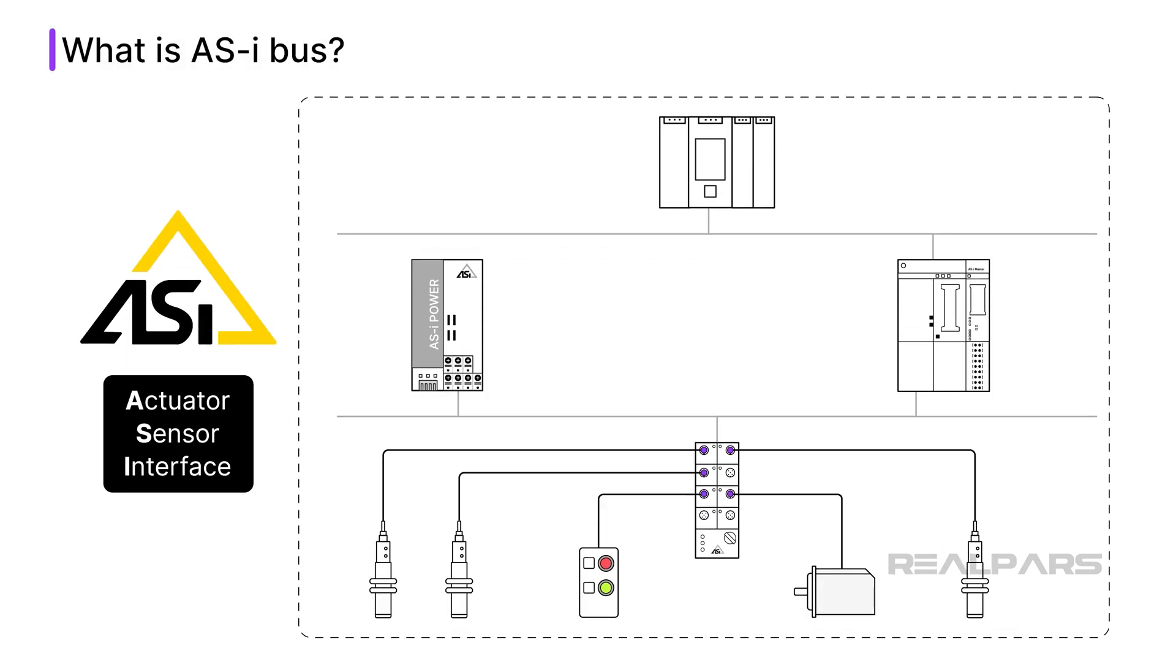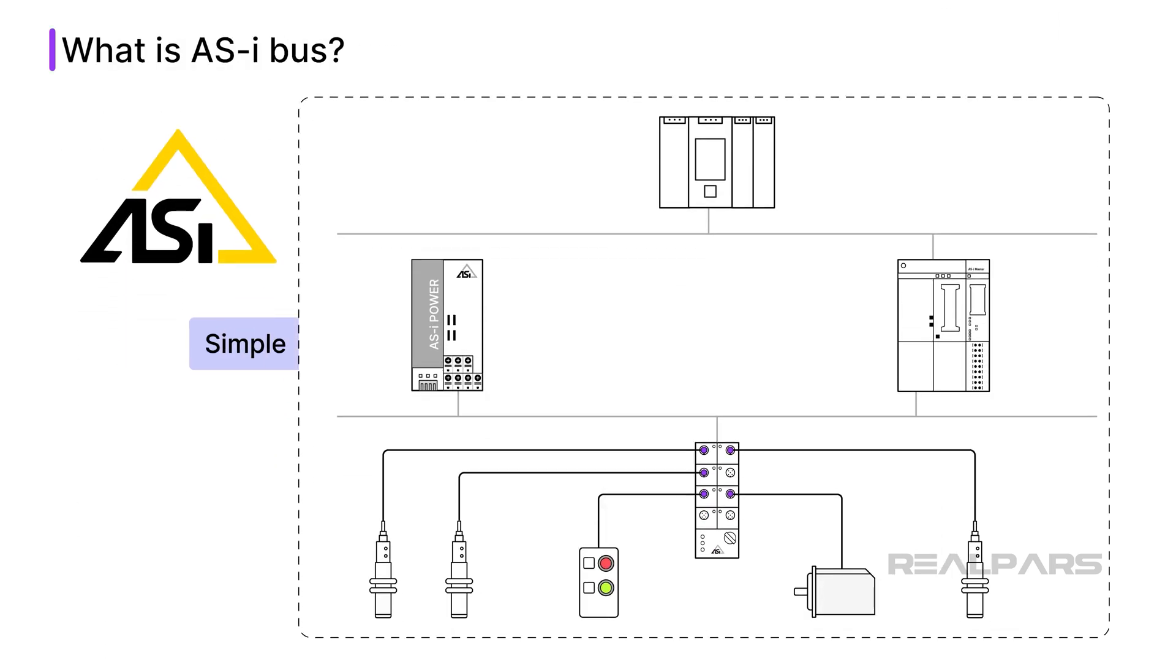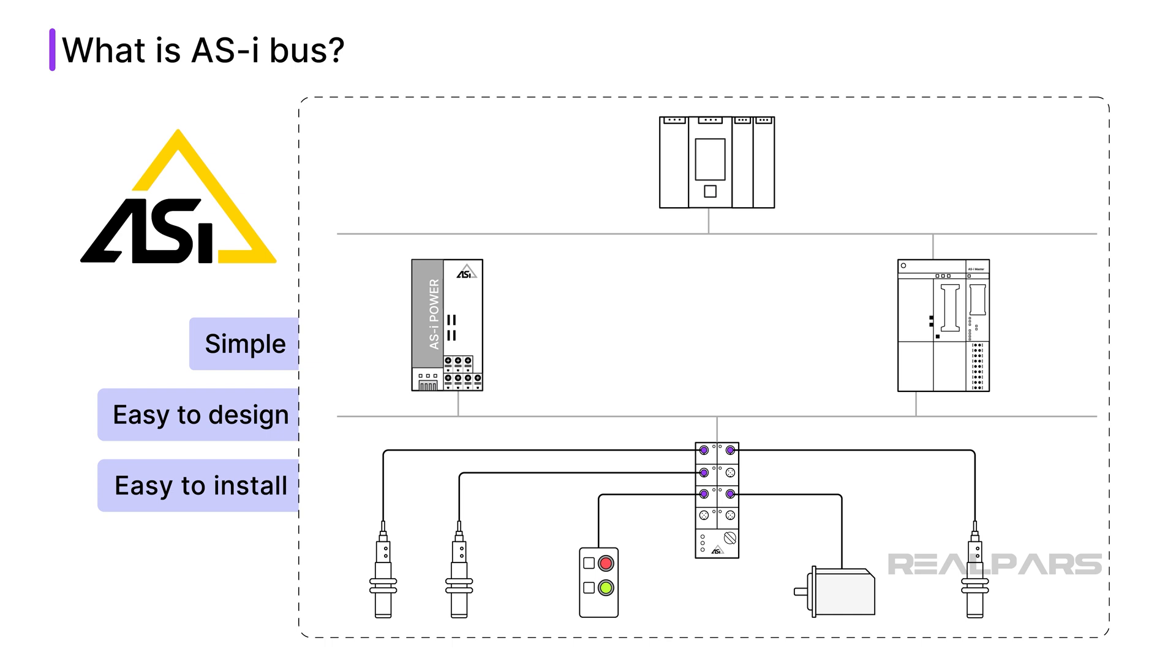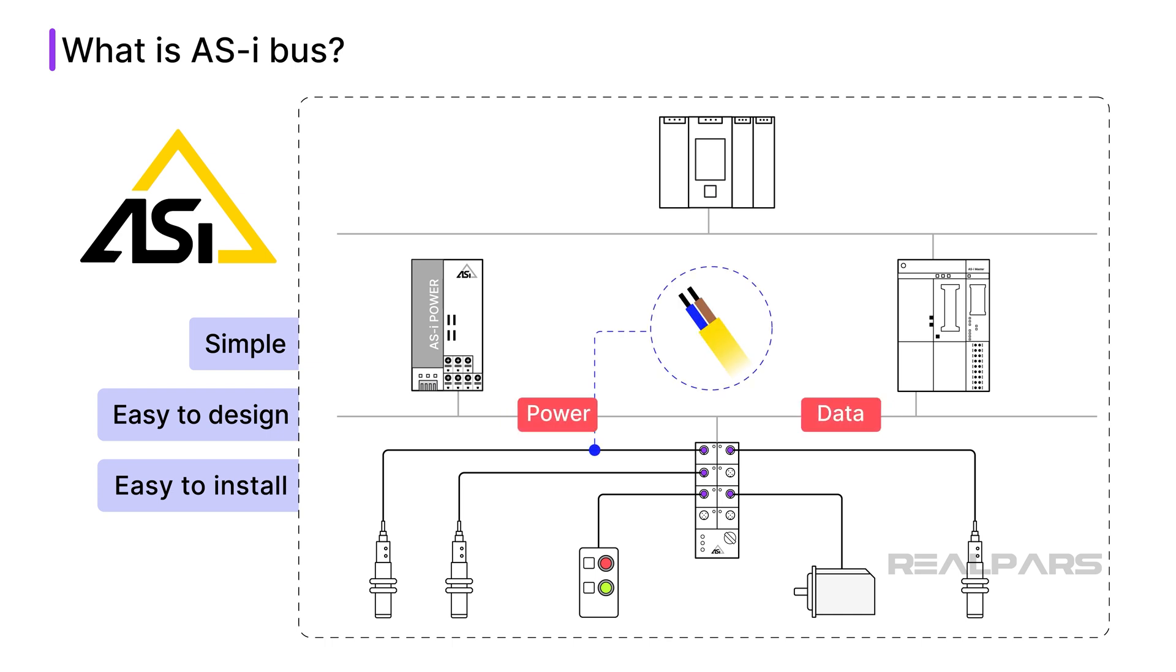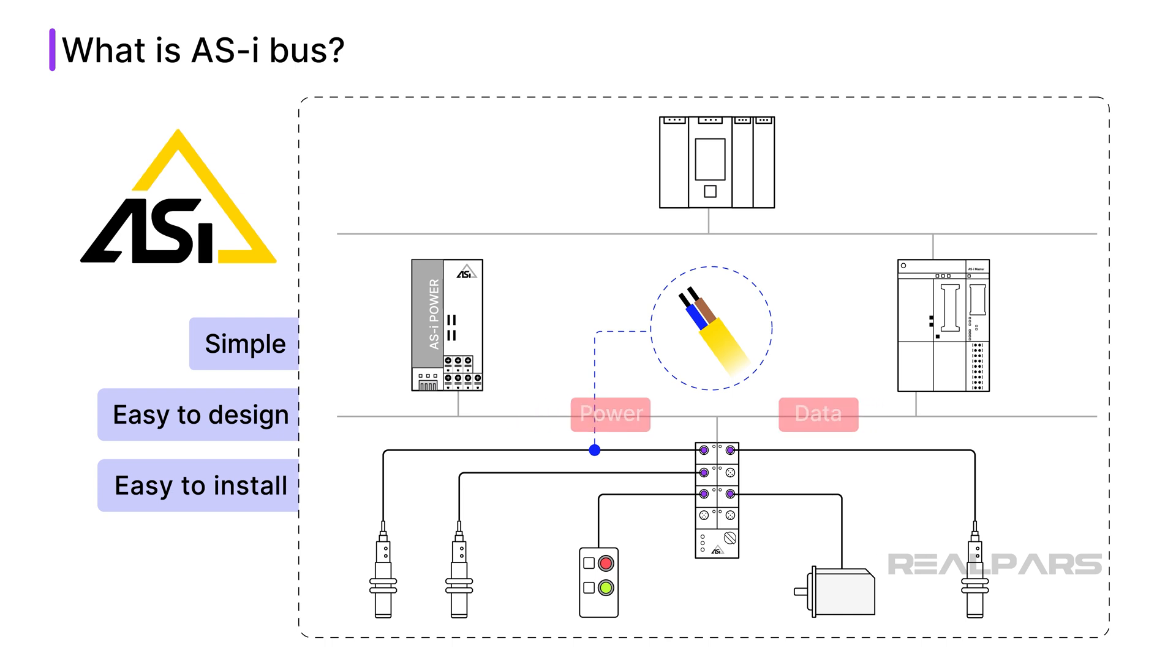AS-i bus is an instrument field bus that is simple, easy to design, and easy to install. AS-i bus was designed to interface with sensors and actuators on the plant floor using a single two-wire cable. Both data and power are transmitted over the same cable. This makes AS-i bus one of the most affordable field bus solutions.